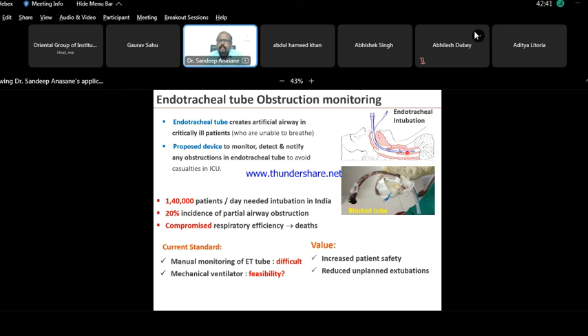When it blocks, a negative pressure forms in the ventilator, because the ventilator keeps pumping air but the air is not delivered to the lungs at the required pressure. So a pressure difference starts. Ventilators are usually designed to detect that negative pressure only when it reaches some particular threshold value. Even then, the clinician or attendant has to attend to the patient within a very small time period and replace the tube. Otherwise, if it goes unnoticed, it becomes a serious situation for the patient.